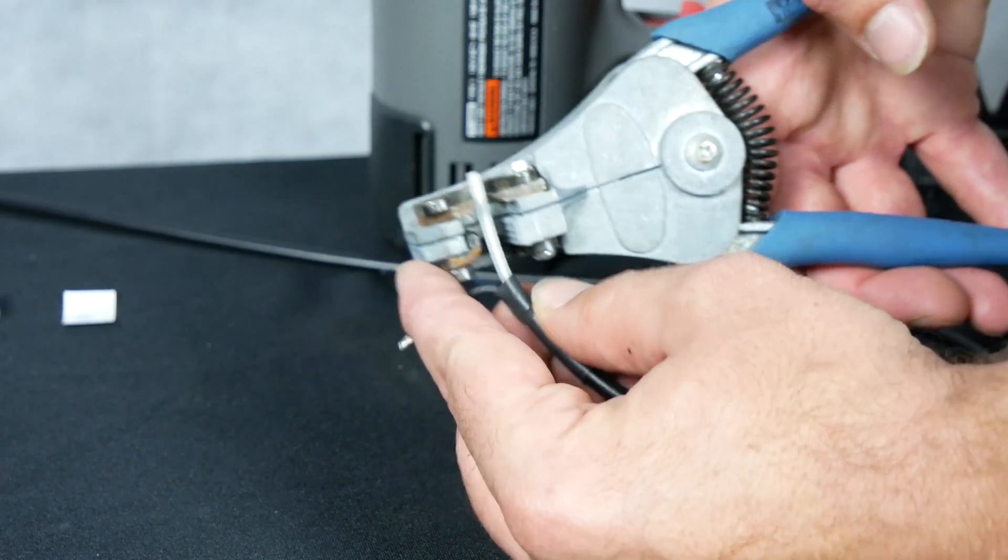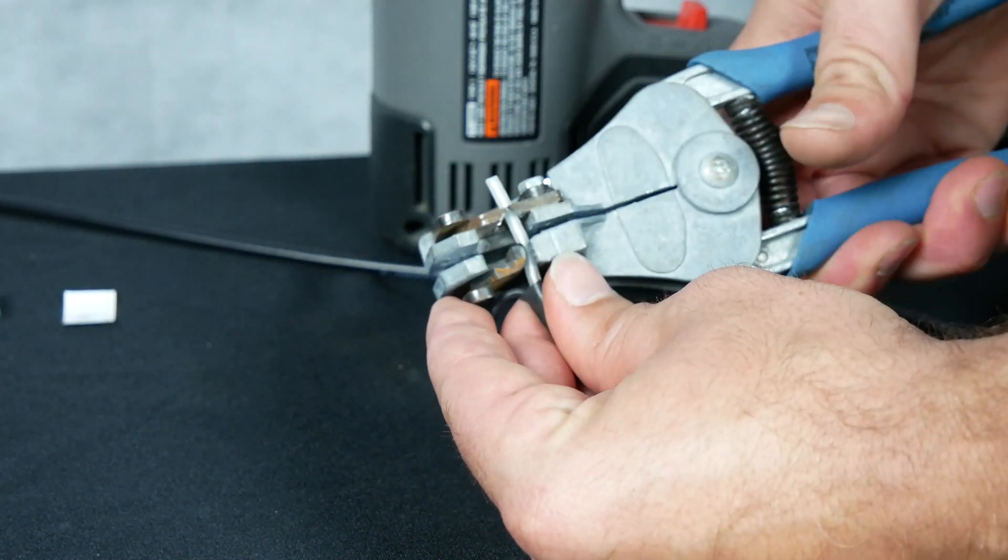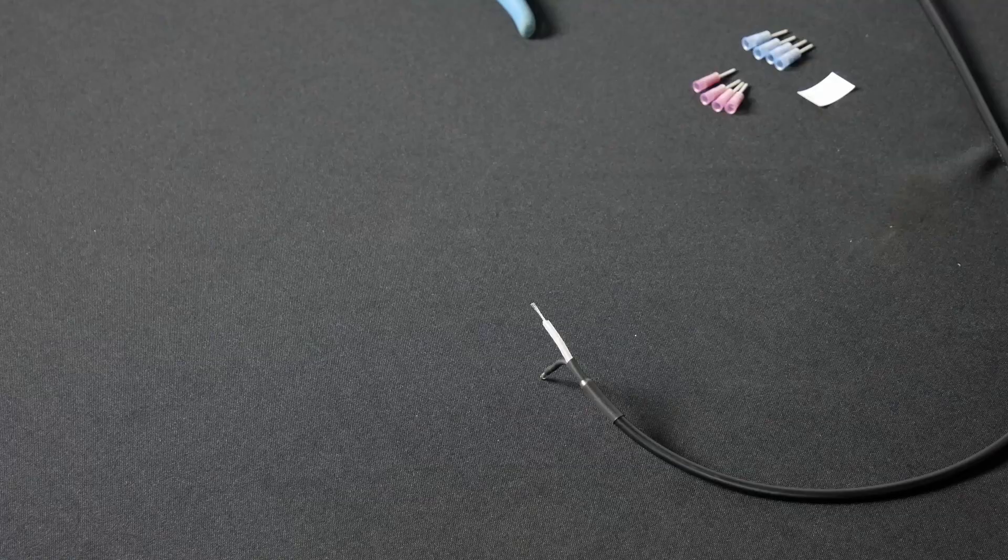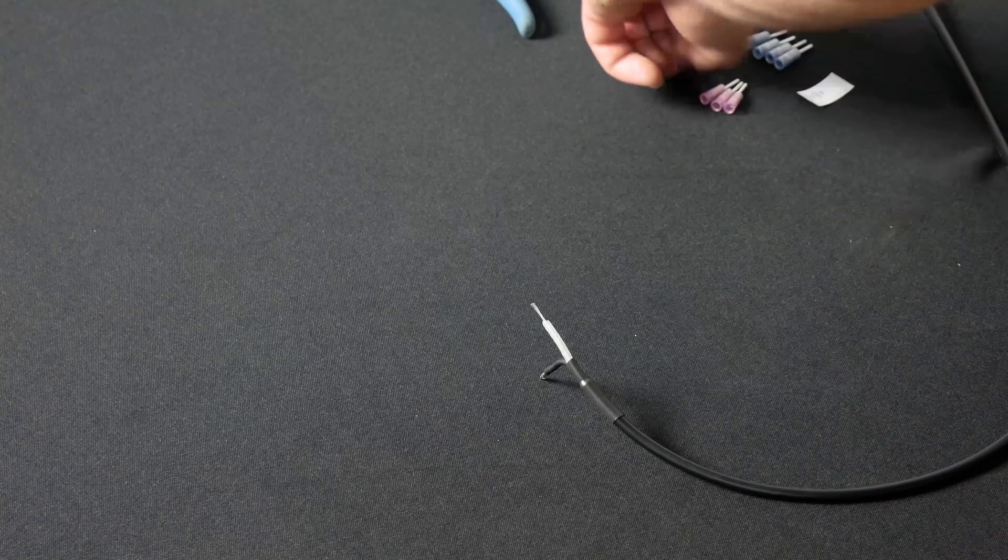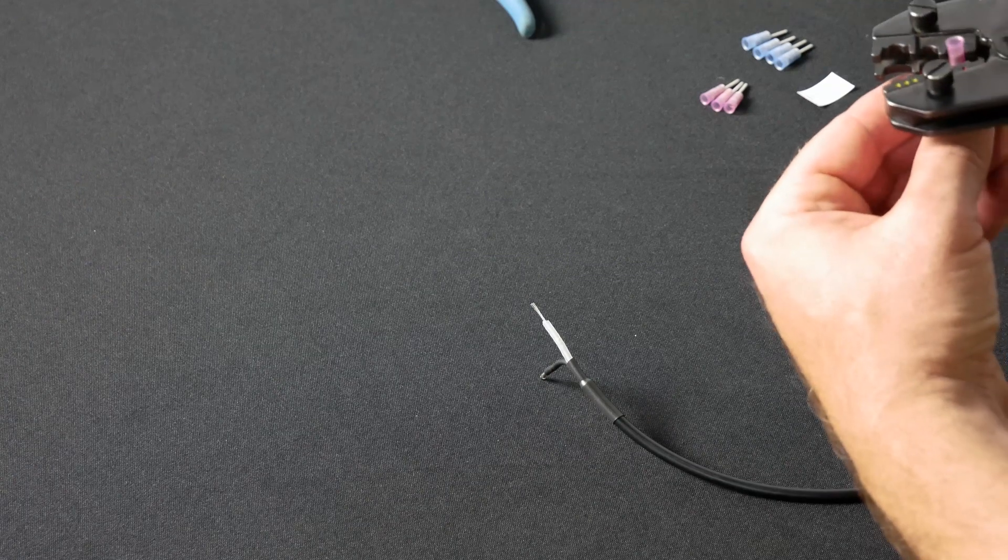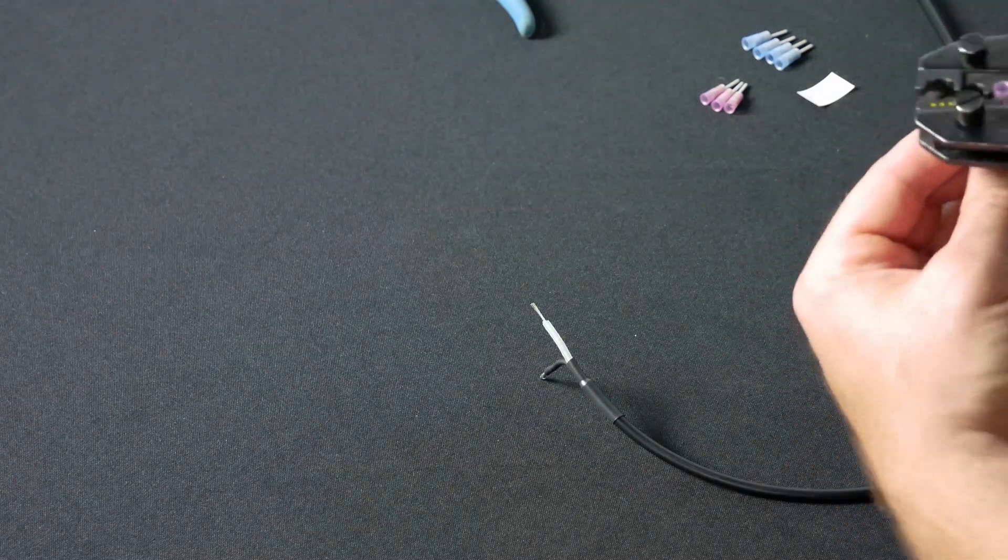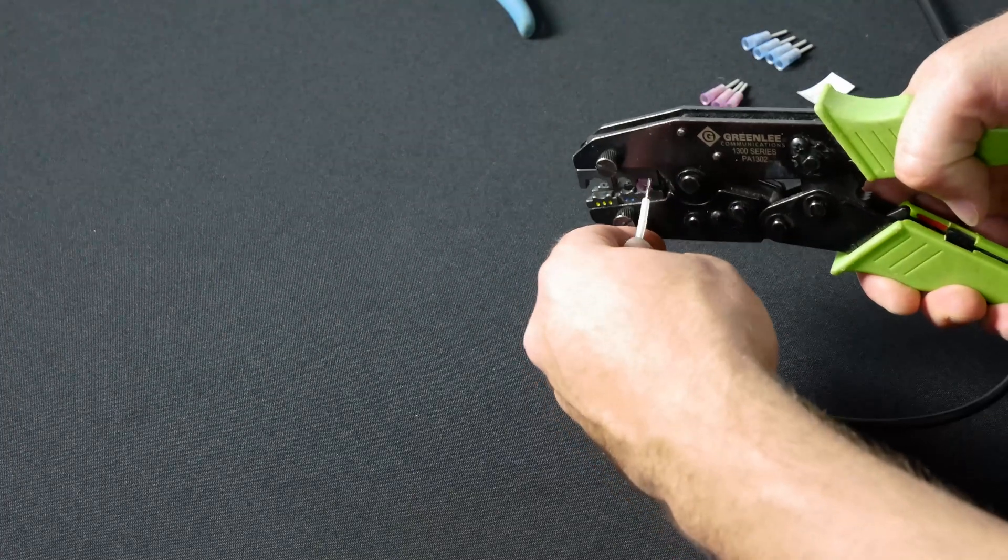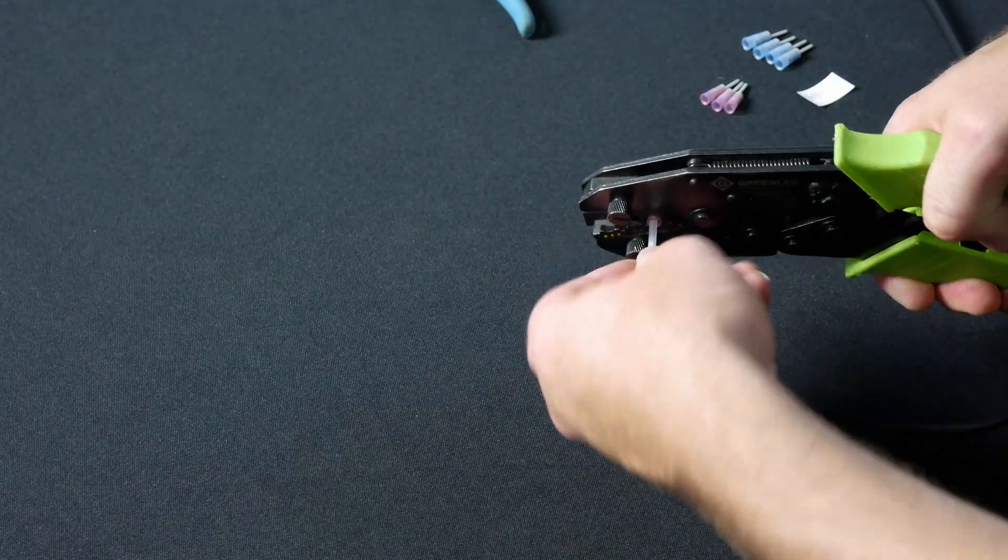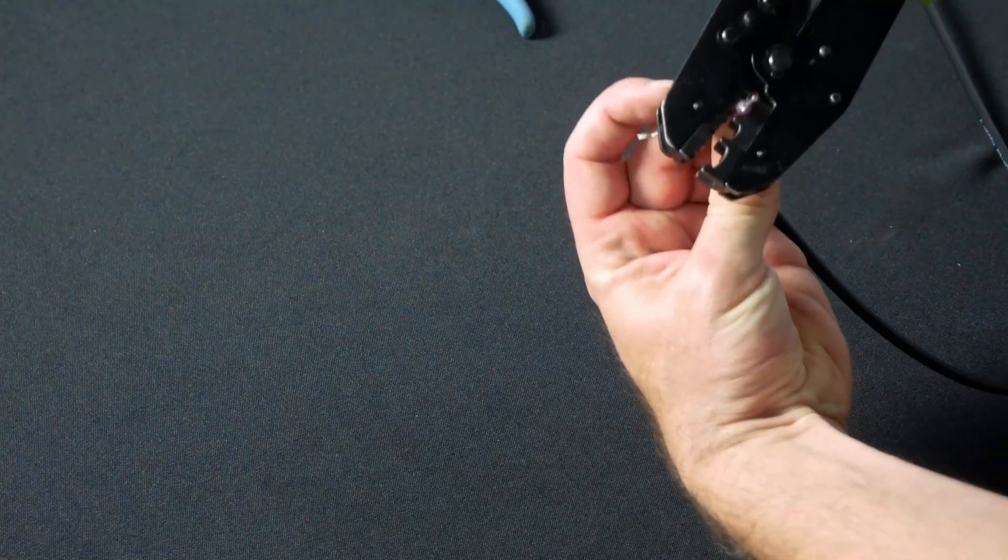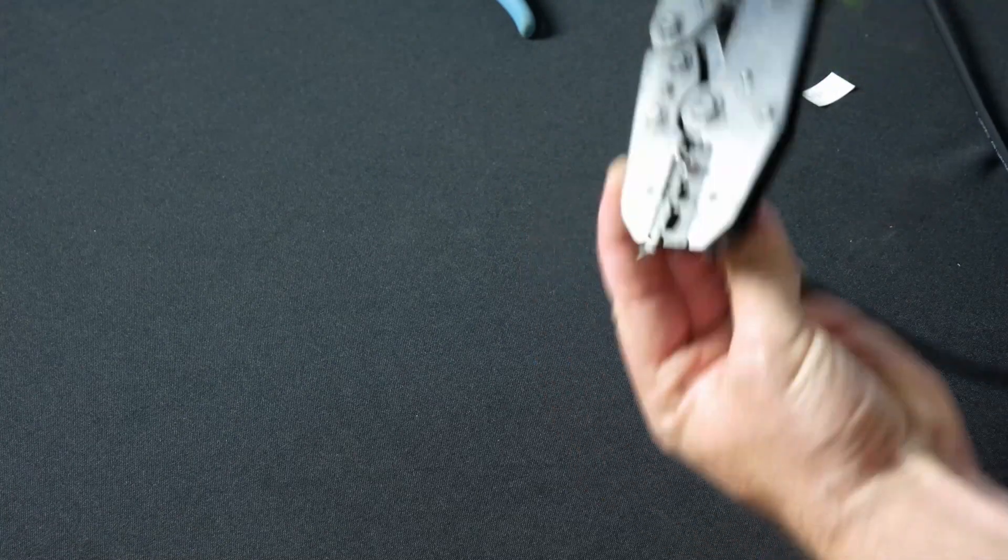Next, strip back the center conductor of the coax so you have enough to crimp your ferrule or terminal onto. Then crimp on your terminal. You want to select the proper size terminal for the conductor you are using. The center conductor generally uses an 18 to 22 pink or red terminal. Make sure you can see the wire through the sight hole at the end of your terminal.